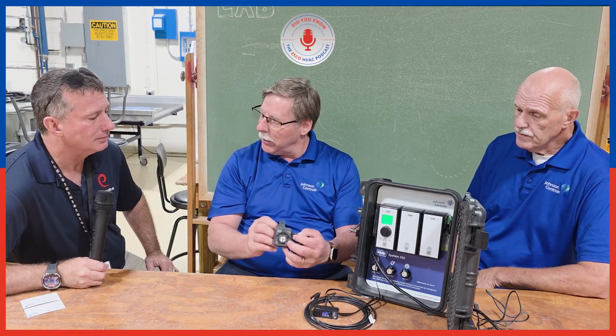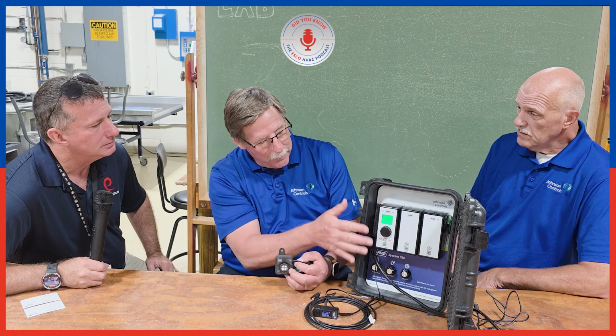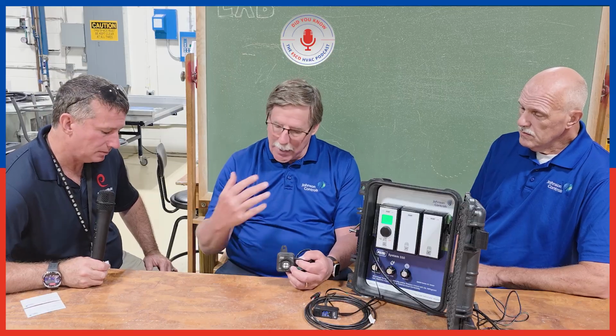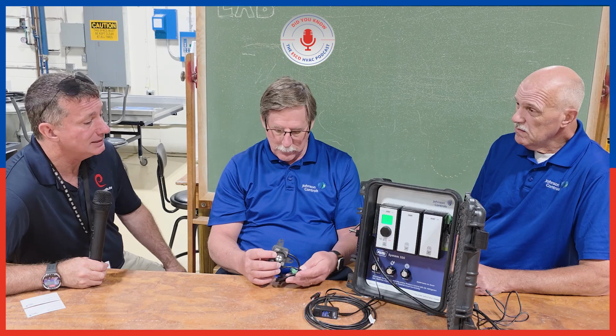The life is 15 years. Because it's communicating through Modbus, it is counting down how many days are left on the sensor. When it gets to 90 days from the end of life, if you just have the controller here, it's going to give you a badge or an alert saying you need to change out your sensor. And then if you're connected to the cloud, you're going to start getting alerts on your smart device. At some point, if you don't change the sensor out, it's going to go end of life, and then your system's going to be down. So that's another point of smart. Smart is not only, is it functioning correctly, but is it within its lifespan? And that's been a big concern of technicians. What is the life expectancy? How often do I need to replace these?